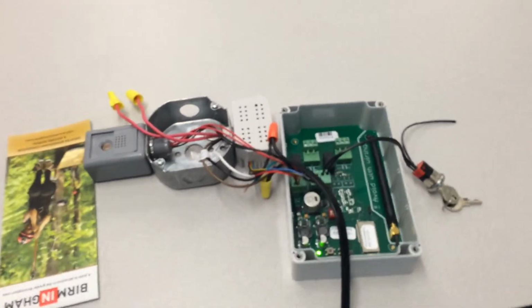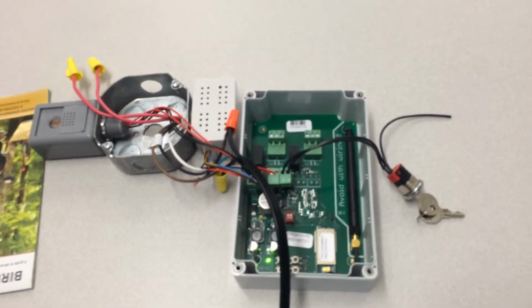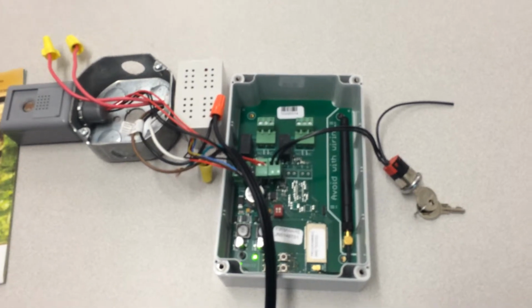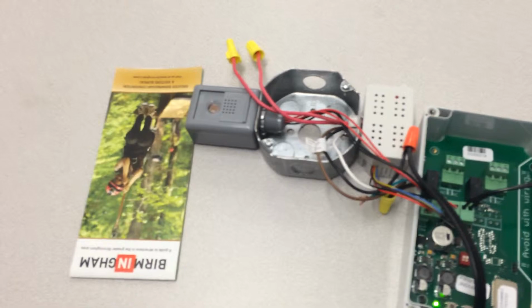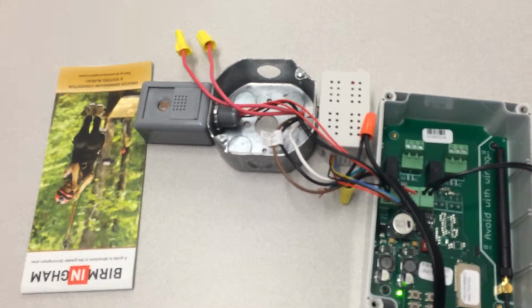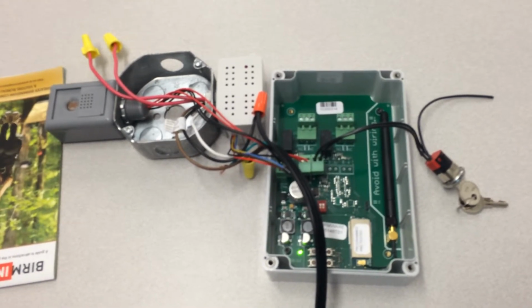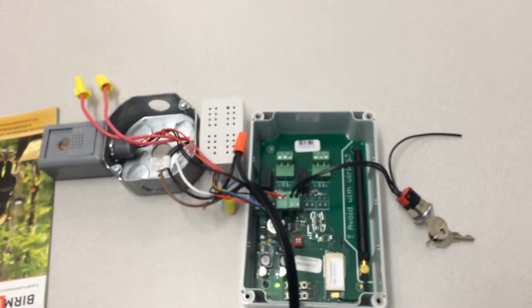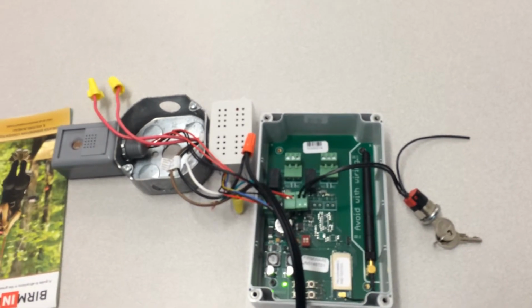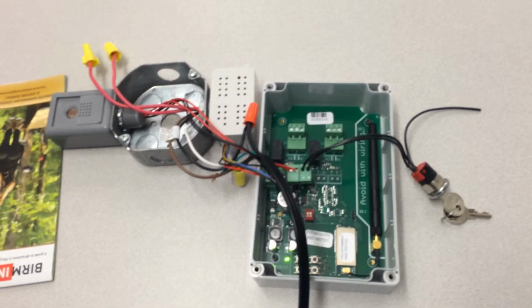The last piece we'd like to show is a wireless input. This is running on the 802.15 IP-based RF network, and this controller has universal inputs and universal outputs, and what we're showing here is two digital inputs, a photocell and a switch. Where we can see this being used may be for monitoring of submeters, using pulse meters, taking it in as an input, and not having to run a wire or a data line or an IP connection down to every meter point.